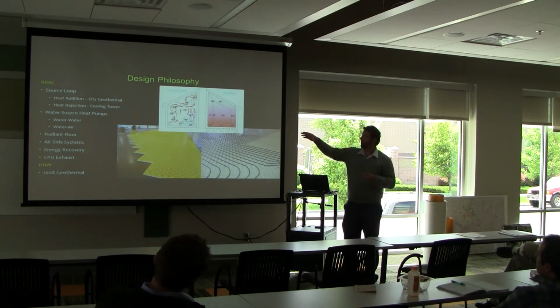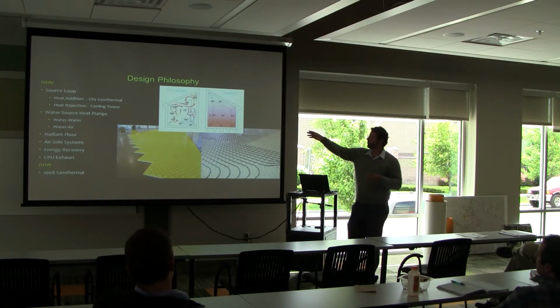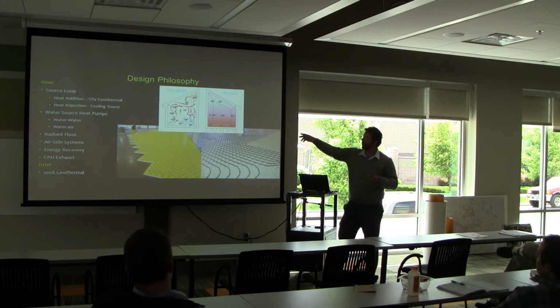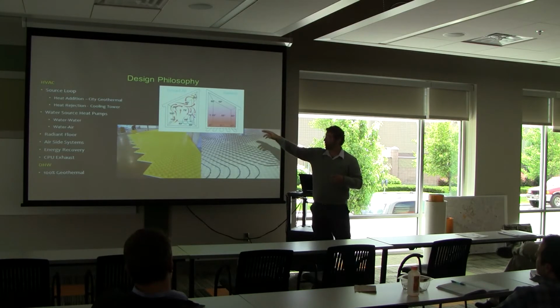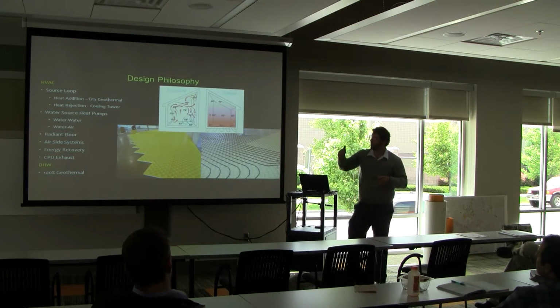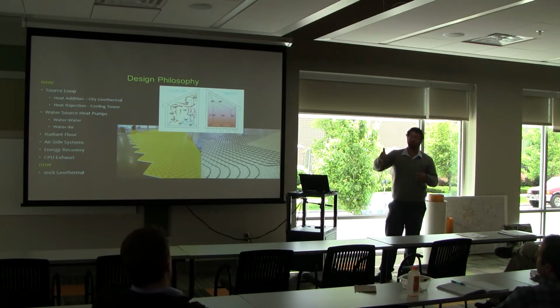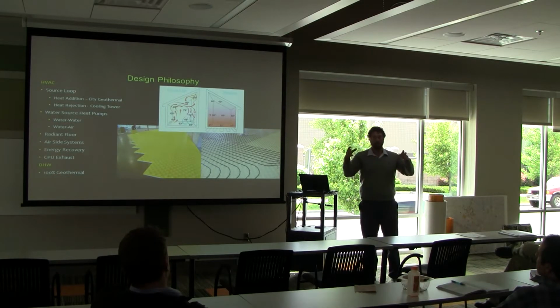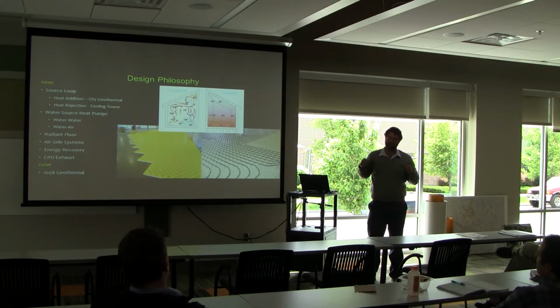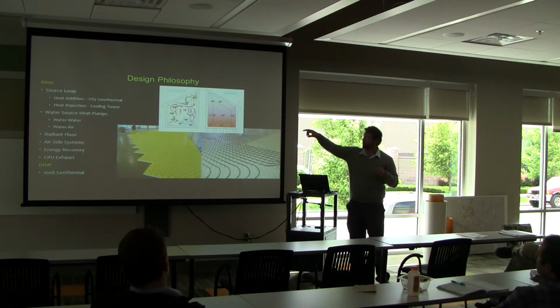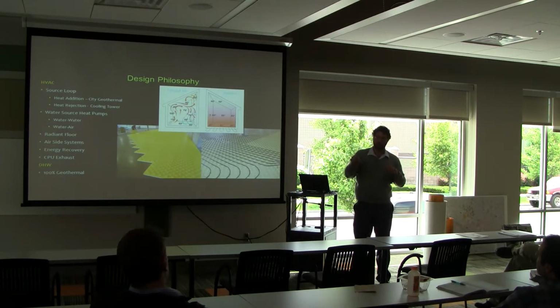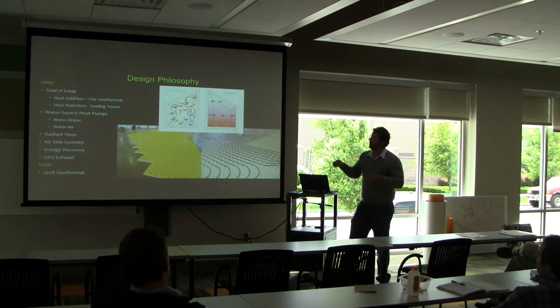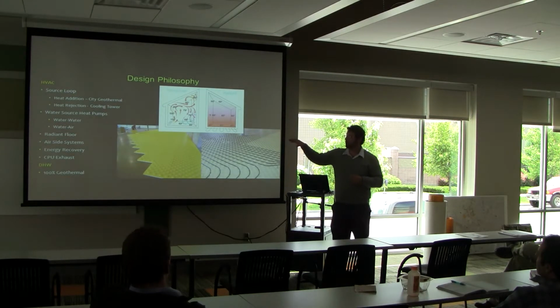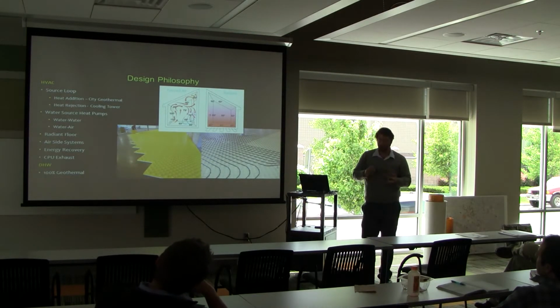We keep that at, by heating. Heat addition water is the city geothermal system. Heat rejection on that source loop is the cooling tower. As heat pumps turn on and off, they're either going to add or subtract heat from the loop. Those two source loop pieces of equipment are there to recover it, however way it needs to have it. There's a combination of water source heat pumps here, both water to water, water to air.